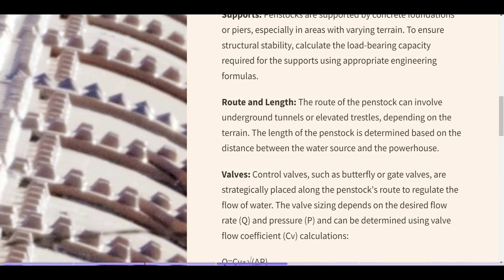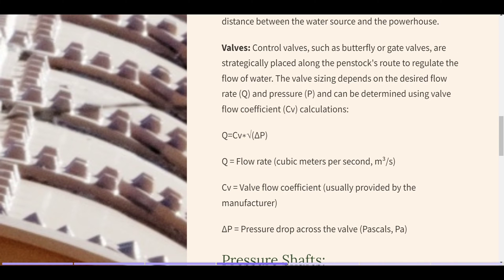Route and length: the route of the penstock can involve underground tunnels or elevated trestles, depending on the terrain. The length of the penstock is determined based on the distance between the water source and the powerhouse. Valves: control valves, such as butterfly or gate valves, are strategically placed along the penstock's route to regulate the flow of water. Valve sizing depends on the desired flow rate and pressure, determined using the valve flow coefficient formula: Q = Cv × √(ΔP), where Q equals flow rate, Cv equals valve flow coefficient, and ΔP equals pressure drop across the valve.